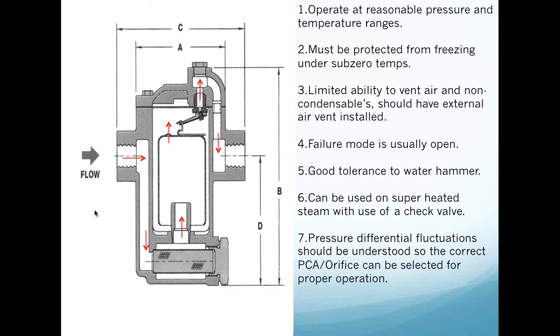But I need you to be patient when you check any steam trap, because there will be an intermittent cycle of this particular technology, so you need to be a little bit on the patient side. They can be used on superheated steam with the use of check valves. Pressure differential fluctuation should be understood, so the correct PCA or orifice can be selected for proper operation.